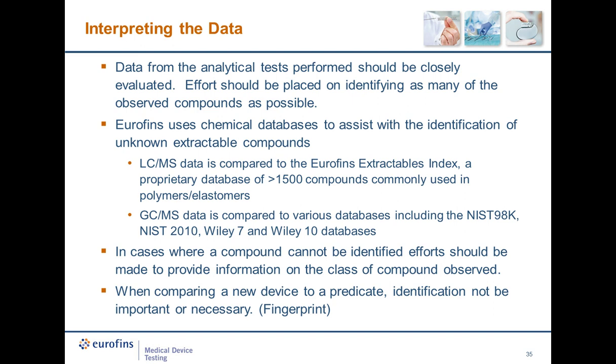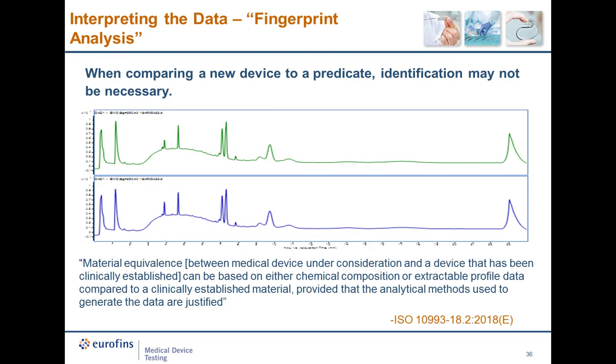One unique instance in which identification of peaks may not be necessary or important is when making a comparison to a predicate device. As I mentioned earlier, chemical equivalence can be determined through the comparison of the extractables profile between a predicate device and new device. The sponsor can perform the same appropriate extraction on both devices and make a comparison between the extraction profiles. If the profile of the new device is less extensive or the same as the established device, then the chemical characterization is complete. However, any extractable present in the new device at a higher concentration than the predicate, or any extractable that is not present in the predicate, needs to be evaluated.